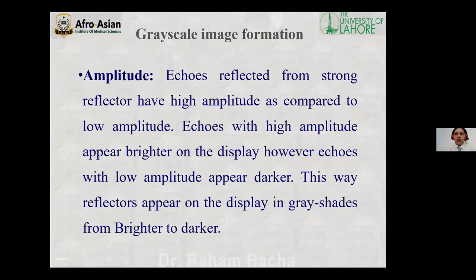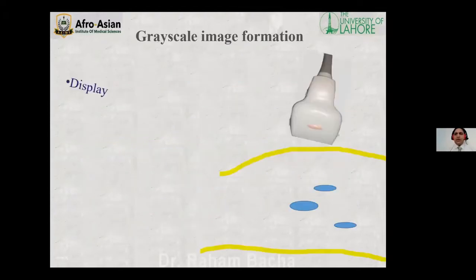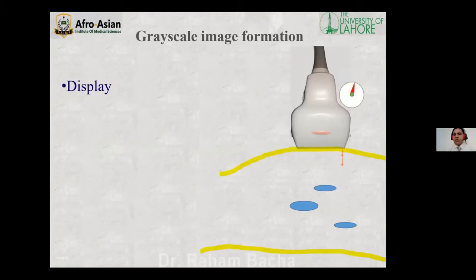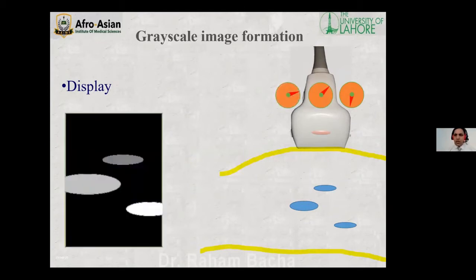The returning sound waves, or echoes, have different amplitudes depending upon the strength of the reflector. Different reflectors have different strengths inside the body, and they reflect sound waves with different amplitudes. Some structures, irrespective of location or distance from the transducer, are strong reflectors, so they will appear bright on the ultrasound screen. Some are weak reflectors, so the sound wave reflected from them will have a low amplitude and will appear black on the display. This way, the ultrasound image appears in gray shades from black to white.